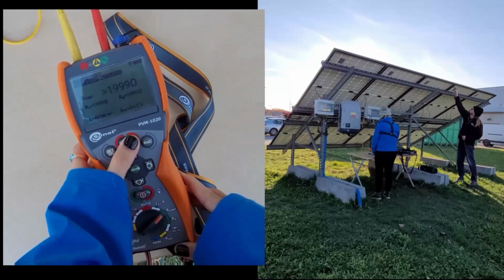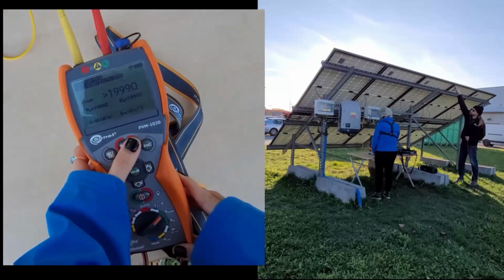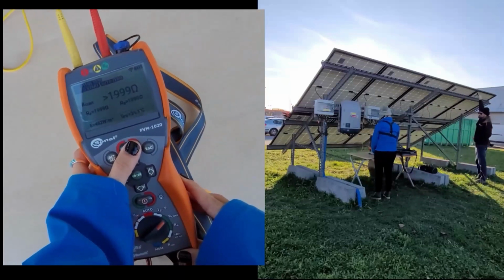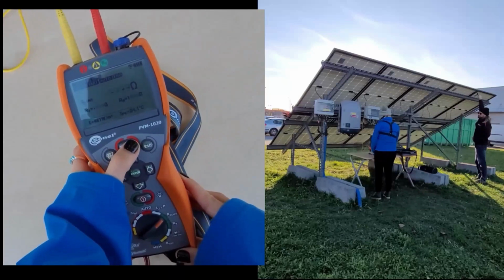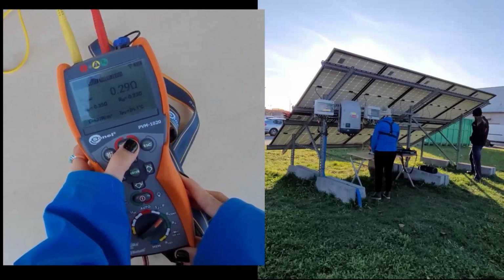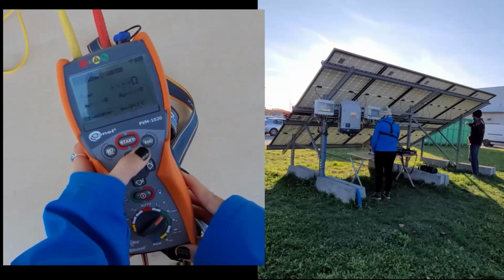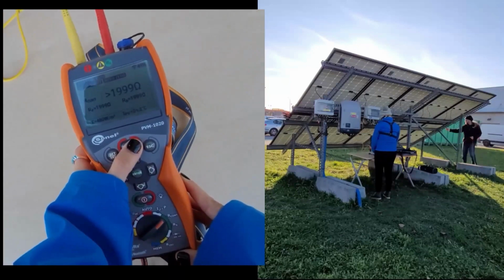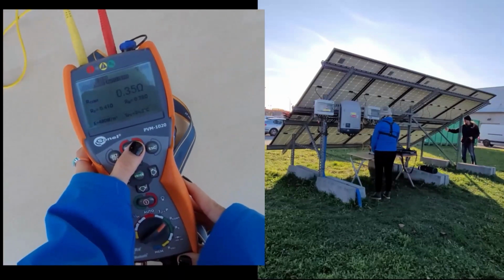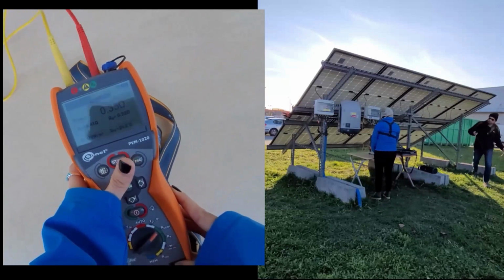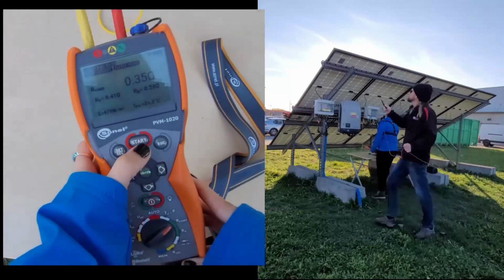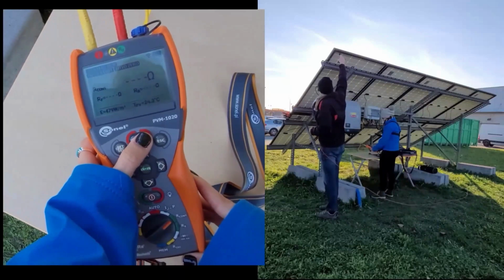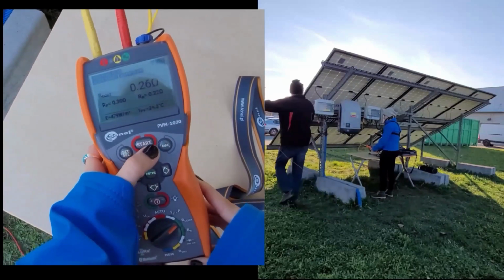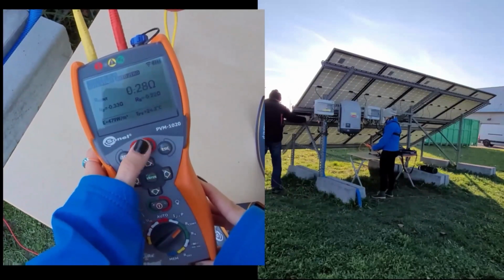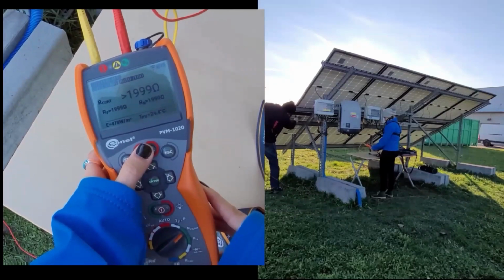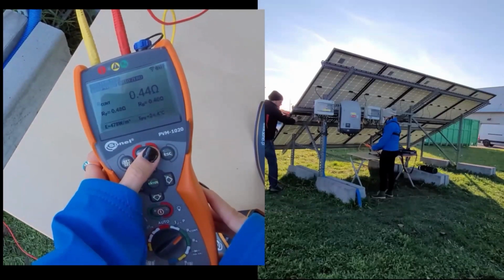As always, we start the measurements by checking continuity. We verify that there is electrical continuity between the grounding or main grounding bar and the construction and panels. As you see, I check all panels and some of the points in construction. What point in construction we should check? You have to decide yourself when you make the visual inspection.